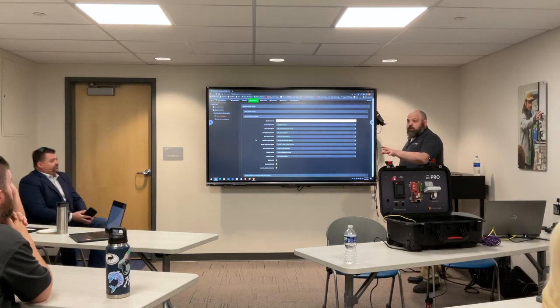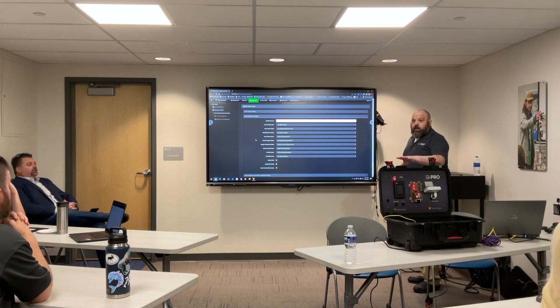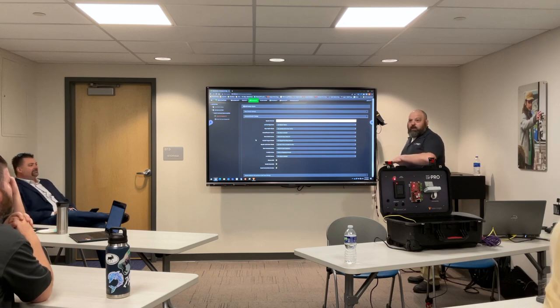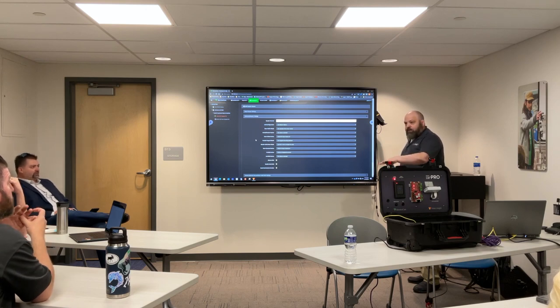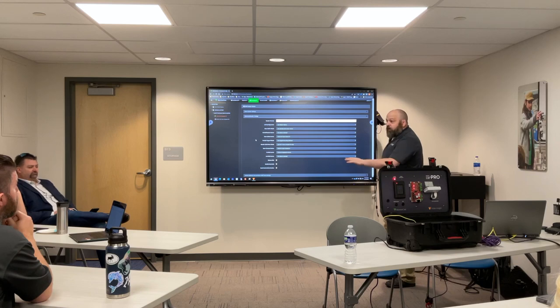And then one other question that you guys had submitted was about ripping out everything you had and replacing it with a standard. I highly recommend not doing that. It is insanely difficult right now to get anything with the word Mercury on it. So if it works, keep it. As long as we'll support it, which is EP1501s, LP1501s, all that same series, we'll probably flash the firmware back to Mercury and we'll be good. We'll be able to pick right up and use it. If it's not broke, let's not get rid of it.